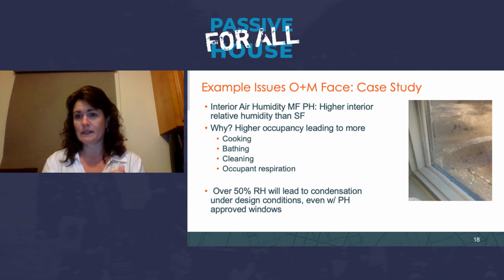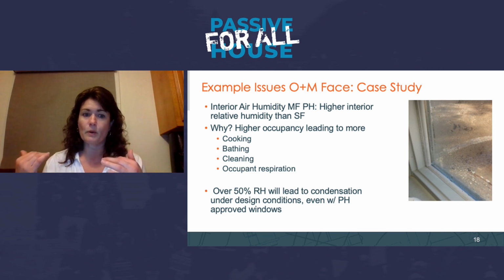Let's talk about relative humidity. This is another thing that O&M staff really needs to be aware of. Interior air humidity in a multifamily passive house can be relatively high compared to a single family home. The reasons for that are, especially in affordable housing, you have higher occupancy, which leads to more cooking, more bathing, more cleaning, and more respiration from occupants, leading to moisture generation into the space. So when you go over 50% RH, you're running into condensation levels, even with passive house approved windows.